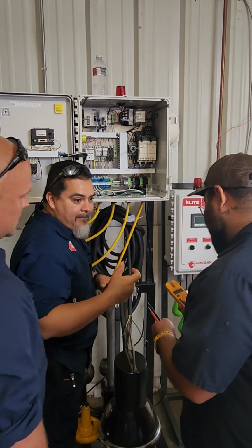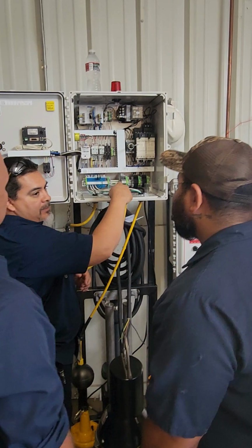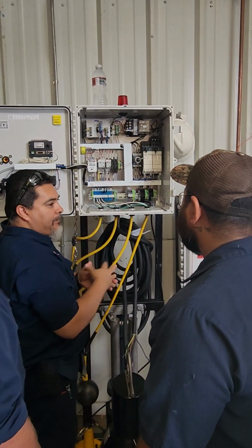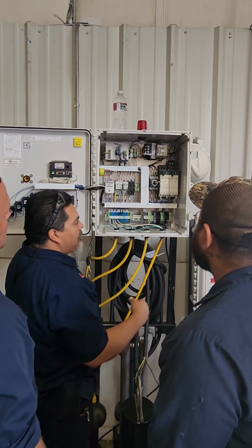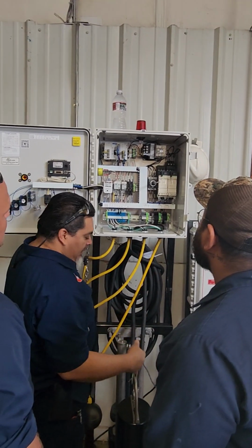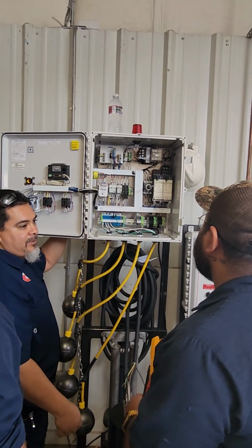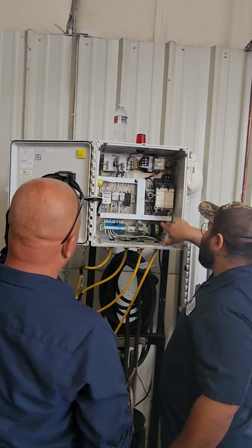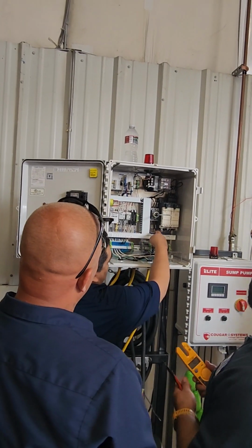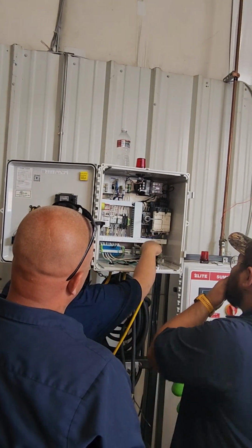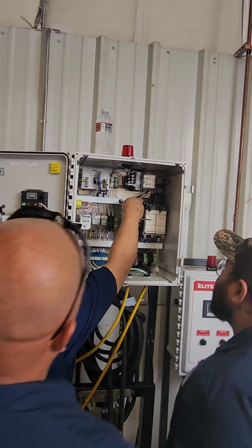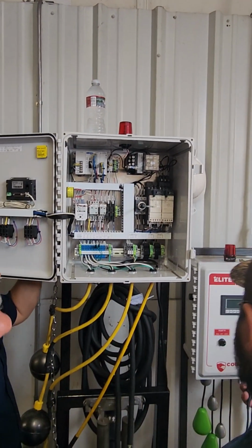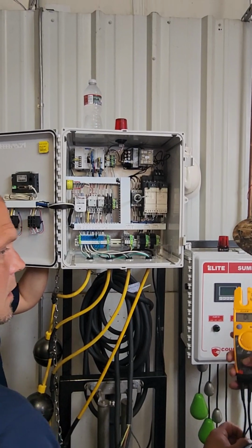Other people have a clamp. You just clamp the first cord, being line 1, line 2, or line 3, and that will give you the readings. But make sure you put the pump on to be able to read it. And if it's overamping, then you know something's locked up. Is there anything up here that I can put the clamp on? For 3 amps you won't be able to fit it, but you can try on those cords or the main incoming power one. As long as that amp number exceeds what the plate says, that's how you know.